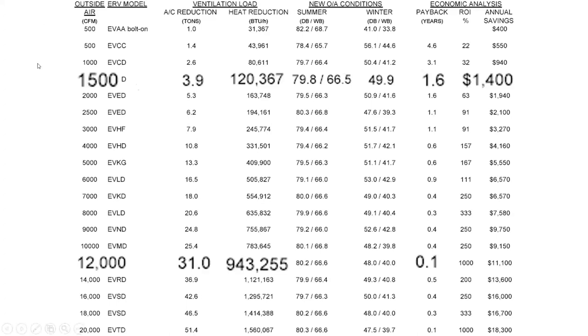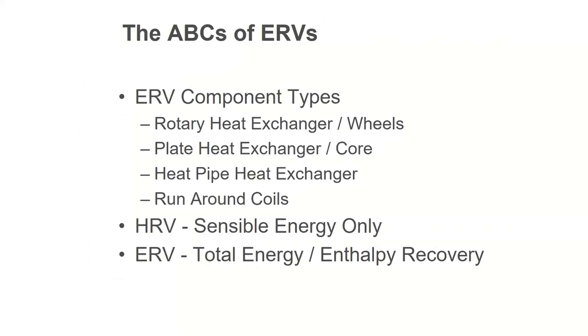But you can see, once you get above 1,000 or 1,500 CFM, the paybacks start getting nice. When you get small stuff, 300, 400, 500, 600 CFM, the paybacks are kind of long, because you're buying all the same electronics and it's all the same amount of effort. It's just you don't have enough outside air to recover from.